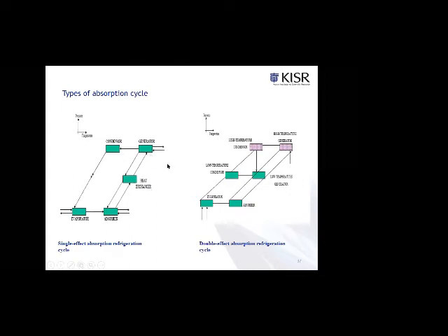What happens in this system, the absorption cycle, is the heat from the sun, if you can imagine having a collector, a flat plate collector or evacuated tube. These two collectors I mentioned before are suitable for this kind of technology, because the single effect absorption cycle needs hot water at 90 degrees. It doesn't need steam. So you can use the very cost effective, feasible flat plate collectors to run it.